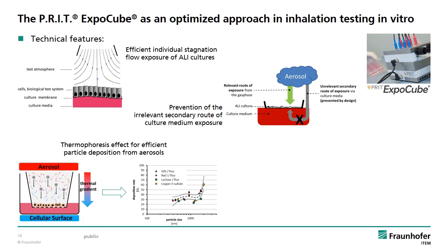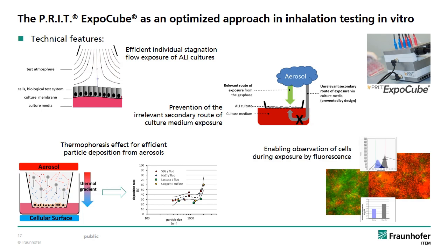By application of a low temperature gradient of 15 degrees centigrade between the aerosol and the exposed cell cultures, it is possible to improve the particle deposition rate to 30% and higher for smaller particle sizes. By principle, this thermal gradient will not affect the cells in any way. Additionally, the ExpoCube offers the unique possibility to combine it with a fluorescence reading system and the exposure effect can be observed non-invasively and online using fluorescence live imaging conditions.